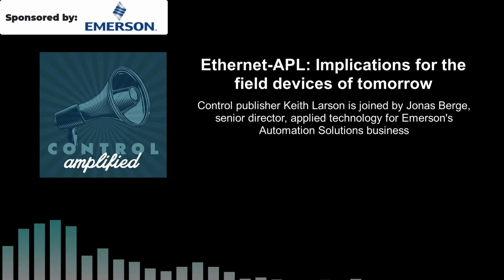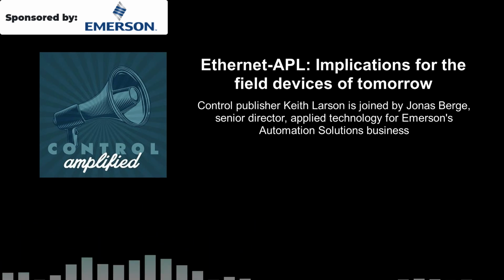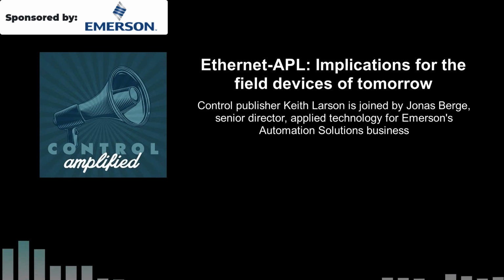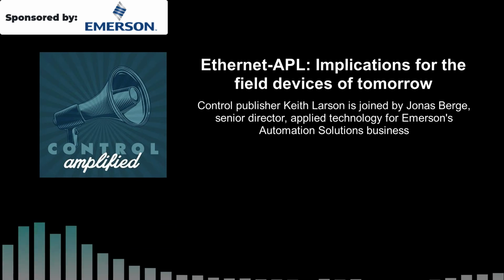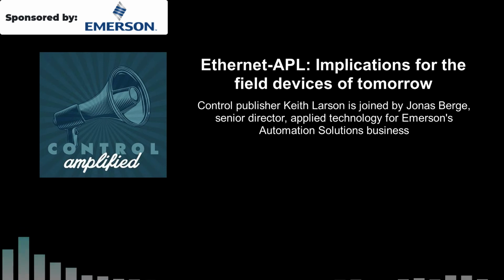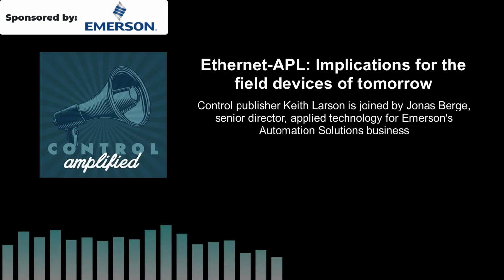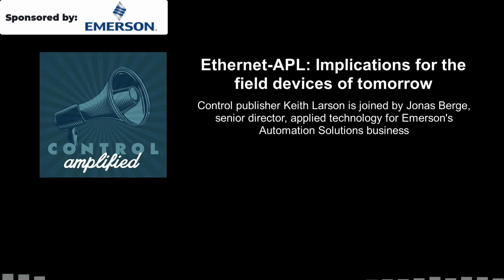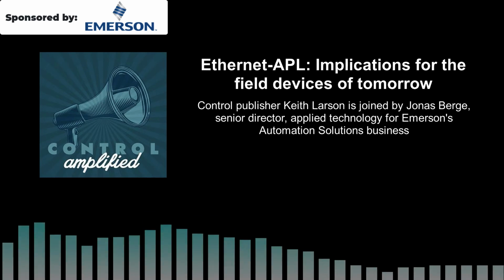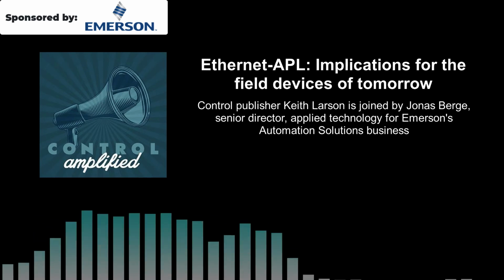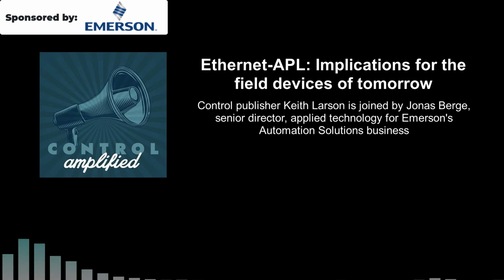I think those will be slower to adopt APL, so for now they have to use 4 to 20 milliamp HART devices. I also believe packaged unit vendors, like boiler manufacturers, will take a while to adopt APL, so they'll ship modules instrumented with 4 to 20 milliamp HART for now. APL makes more sense for certain instrument types than others, so it'll be a while before everything is available in APL.